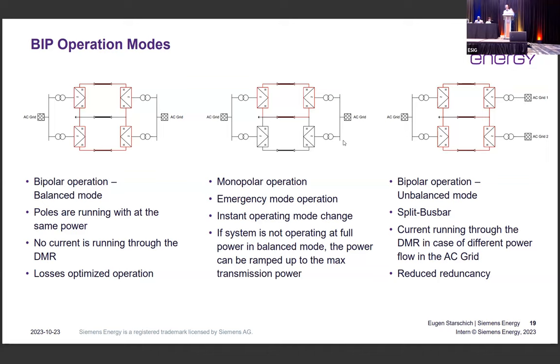One of the features of the bipolar systems is called split bus bar operation and unbalanced mode, which means that at one side, the bipoles are connected to one AC grid, but at the other side, they can be connected to different AC grids. So these AC grids don't need to be synchronized. They can be different unsynchronized grids or different parts of the same AC grid, which are not supposed to be connected. This gives flexibility in the operation. If you collect the energy and transmit it, but you want to feed the energy into different places, you don't need to build two systems. You can still run with one bipolar system, but connect at the other end to two different AC grids.